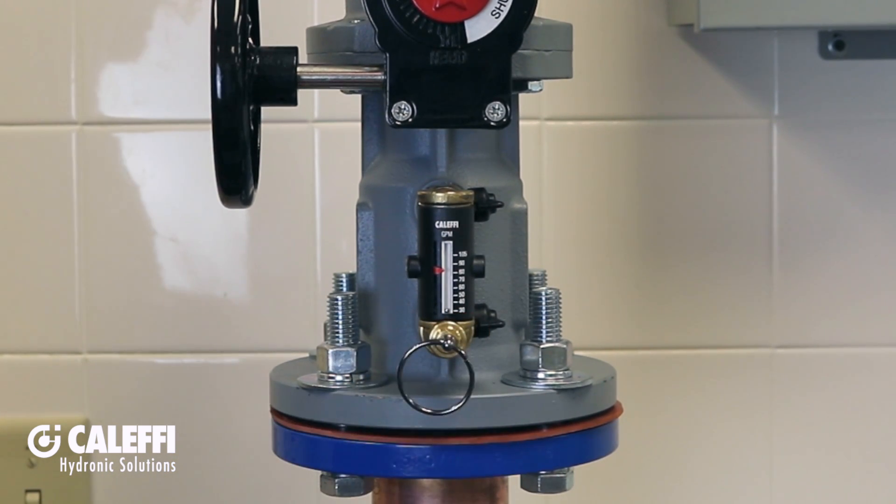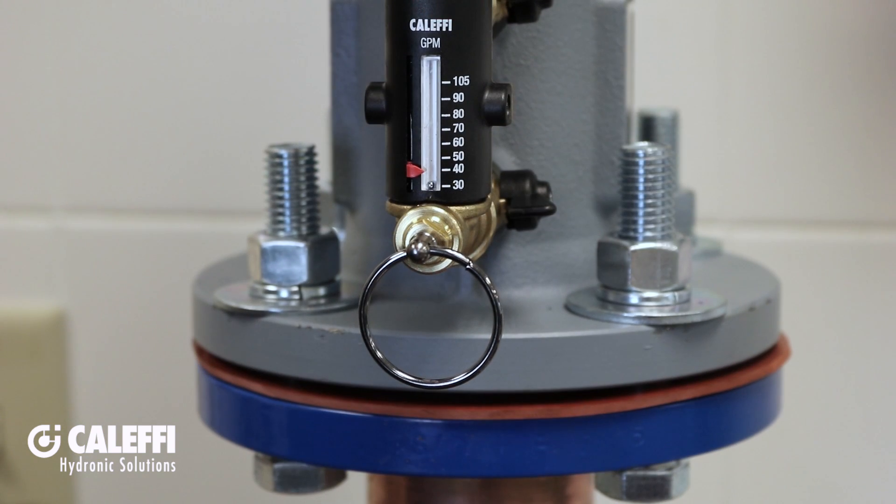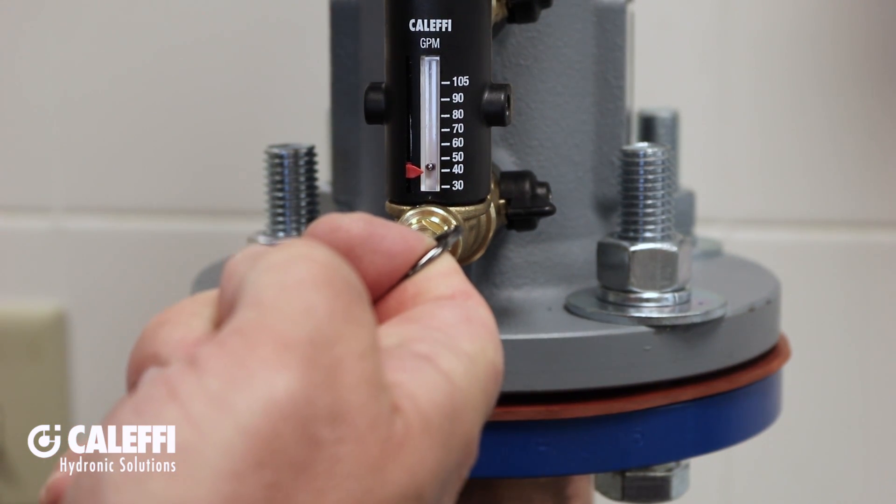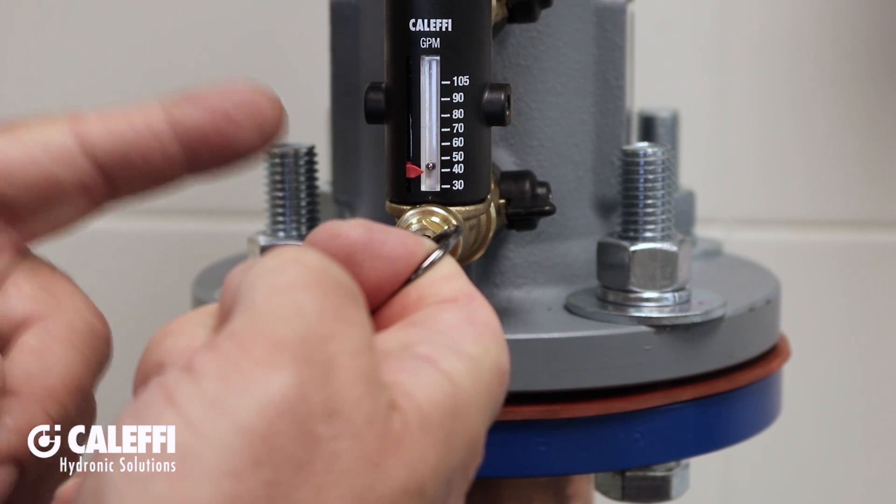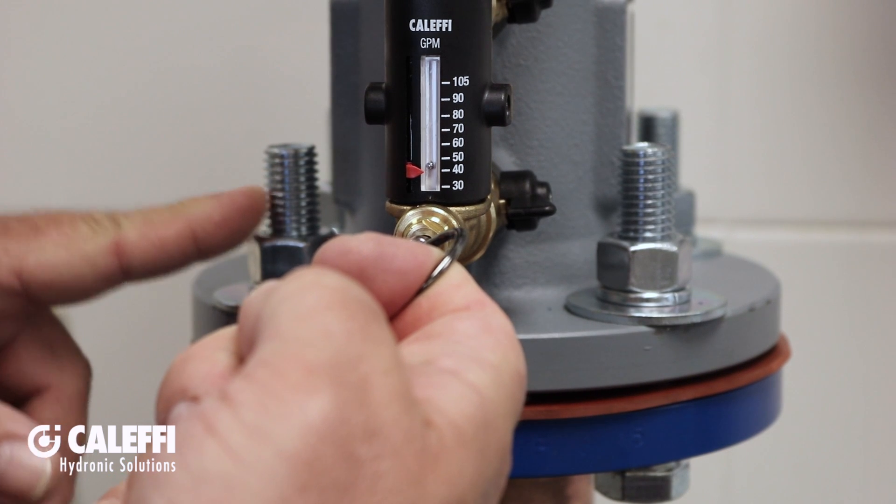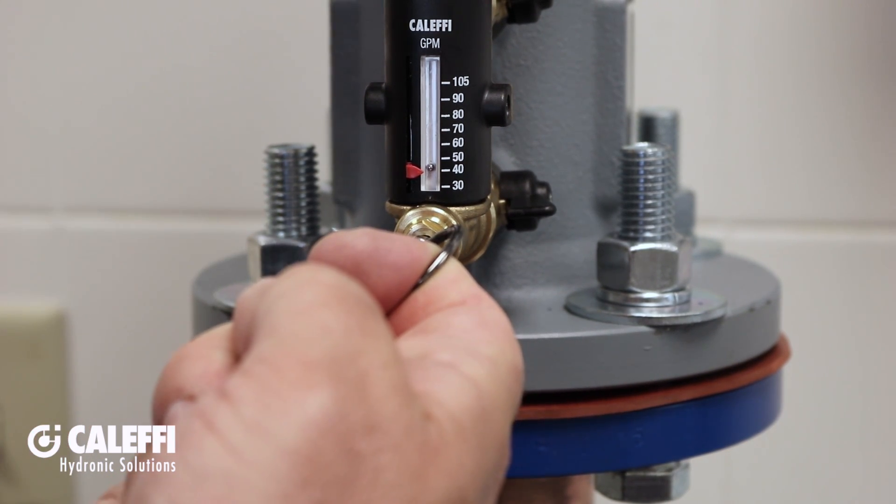Let me show you how to balance the circuit using the quicksetter. With the system pumps running, all I'm going to do is pull this pin. What that does is it opens a small bypass valve which diverts a portion of the system fluid in the main pipe through the flow meter.